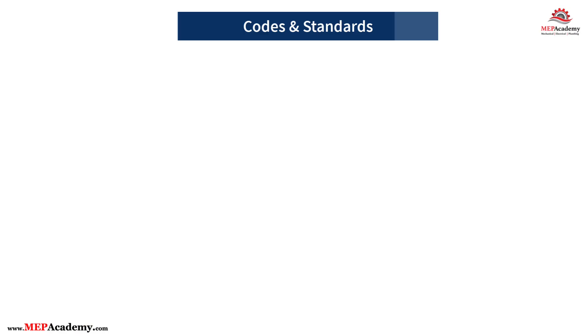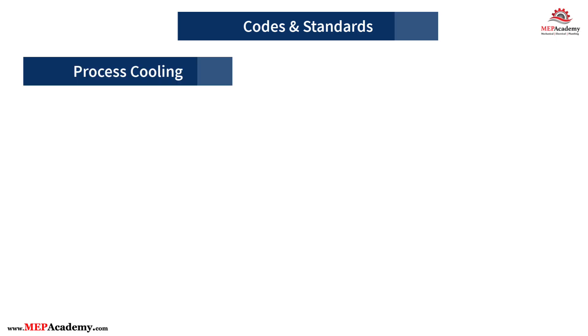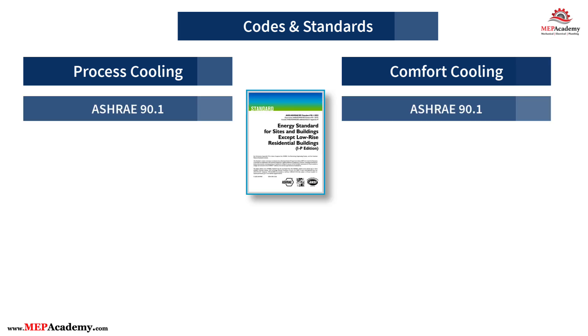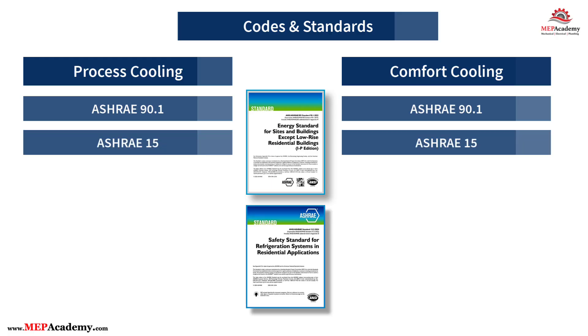Codes and standards governing process cooling versus comfort cooling: both types of cooling systems must adhere to industry codes and standards, though their regulatory frameworks differ. Process cooling standards include ASHRAE 90.1, the energy standard for buildings, which provides guidelines for energy efficiency in industrial processes, and ASHRAE 15, the safety standard for refrigeration systems, which governs refrigeration safety in process cooling applications.